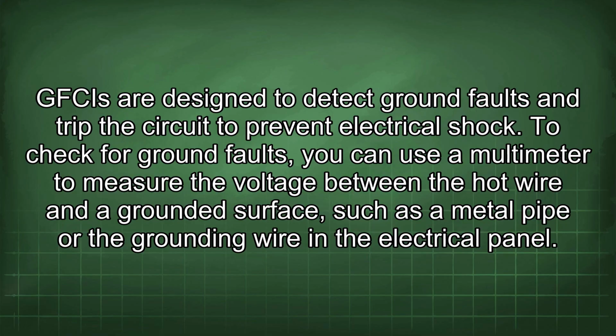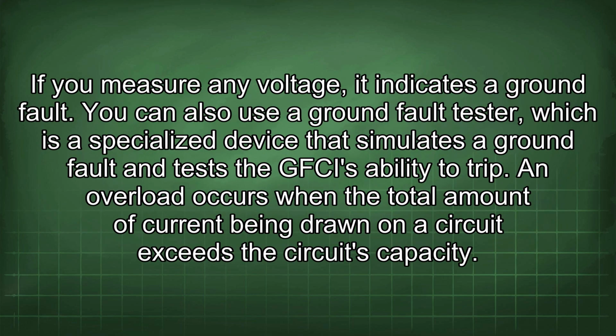To check for ground faults, you can use a multimeter to measure the voltage between the hot wire and a grounded surface, such as a metal pipe or the grounding wire in the electrical panel. If you measure any voltage, it indicates a ground fault. You can also use a ground fault tester, which is a specialized device that simulates a ground fault and tests the GFCI's ability to trip.